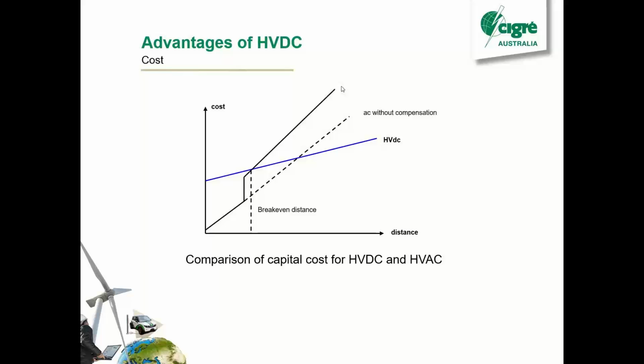There's also this graph that gets pulled out quite a bit. Once you get over a certain distance, it is actually cheaper to go HVDC instead of AC, and that's due to the losses, if you capitalize the losses over the lifetime of the link. So with HVDC there is an entry cost, and that's basically your converters. You have to buy your converter stations at each end, so that's pretty much a steady cost. And then as your distance goes up, that's the cost of your line going up.